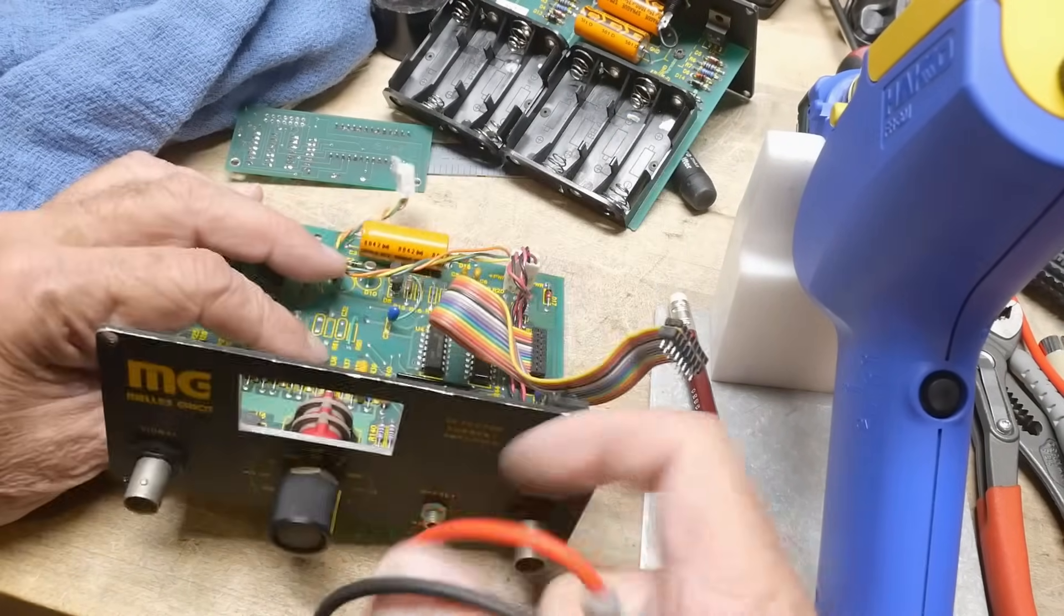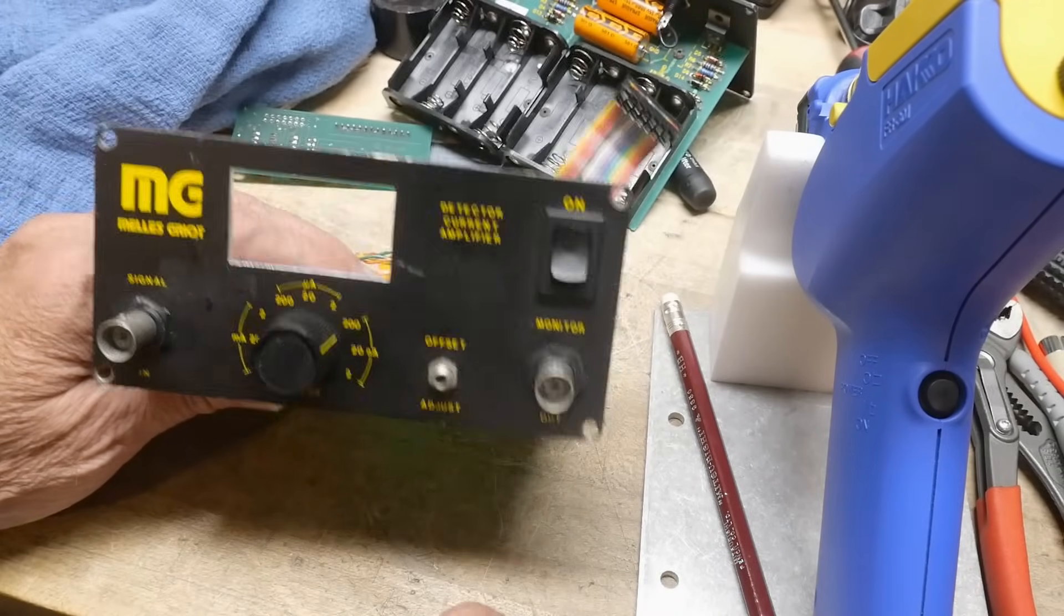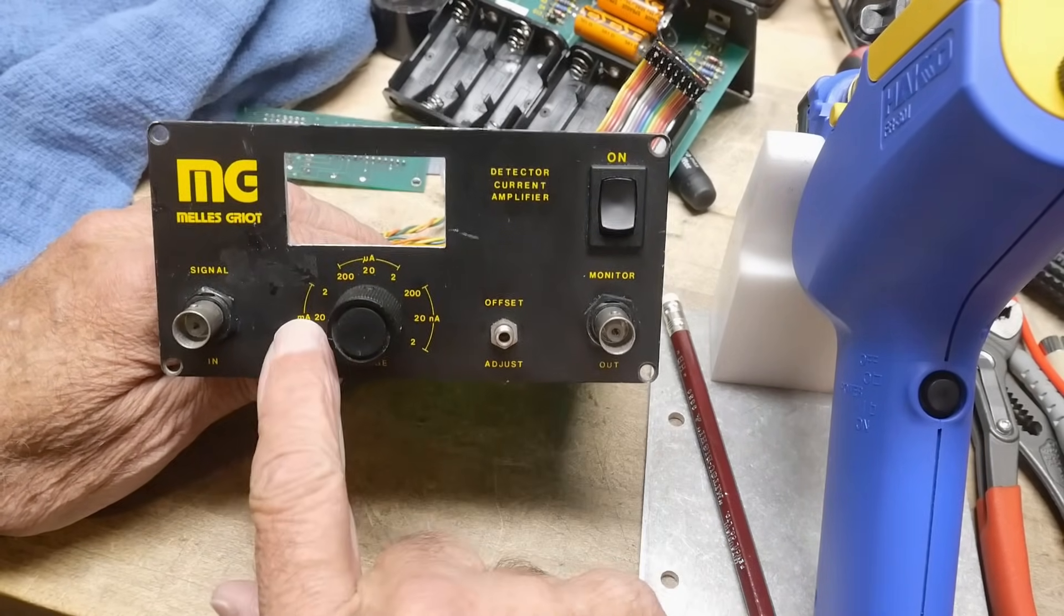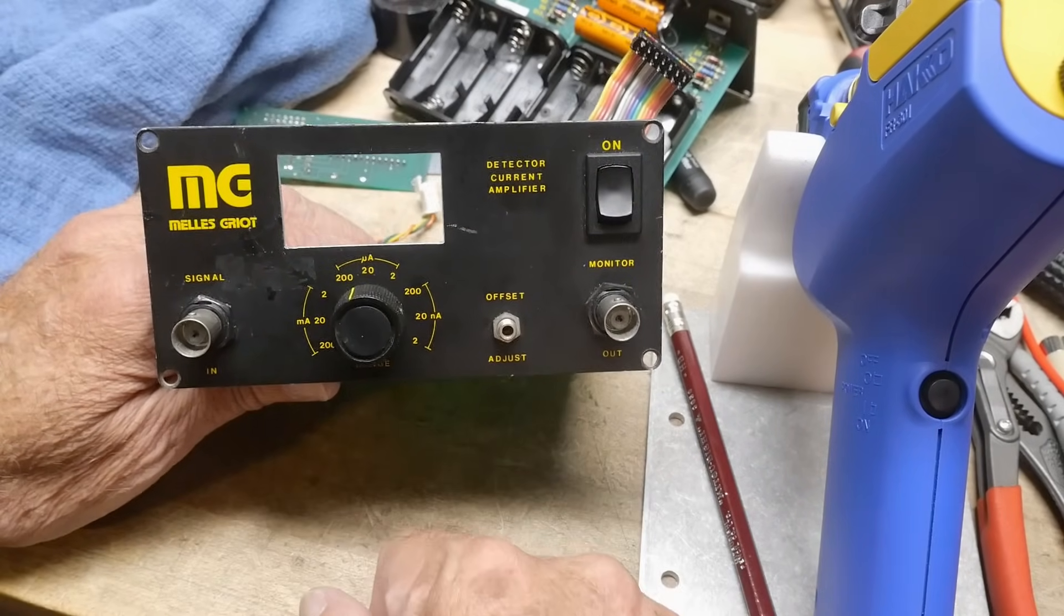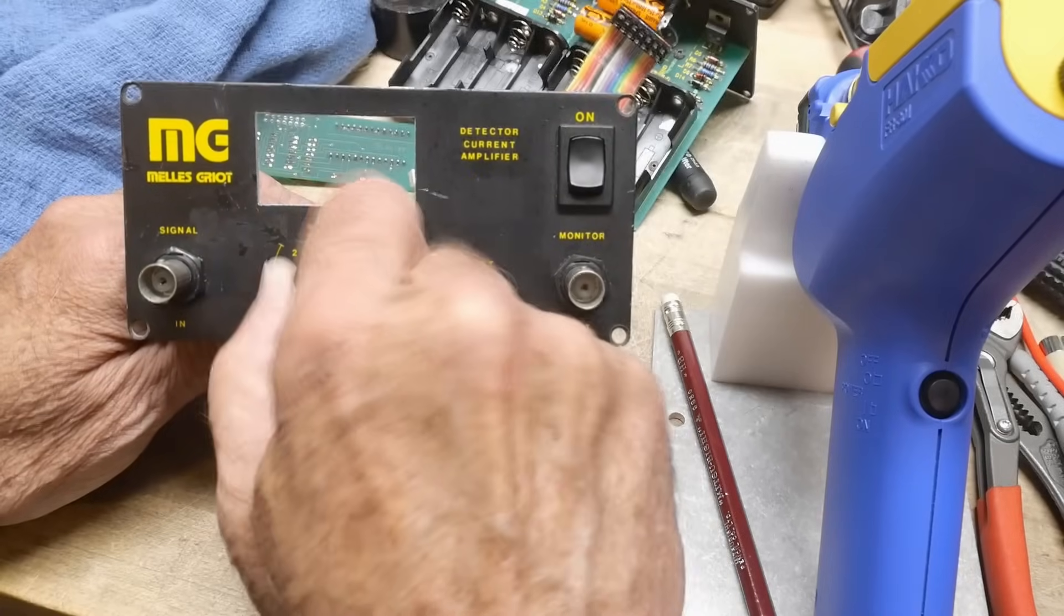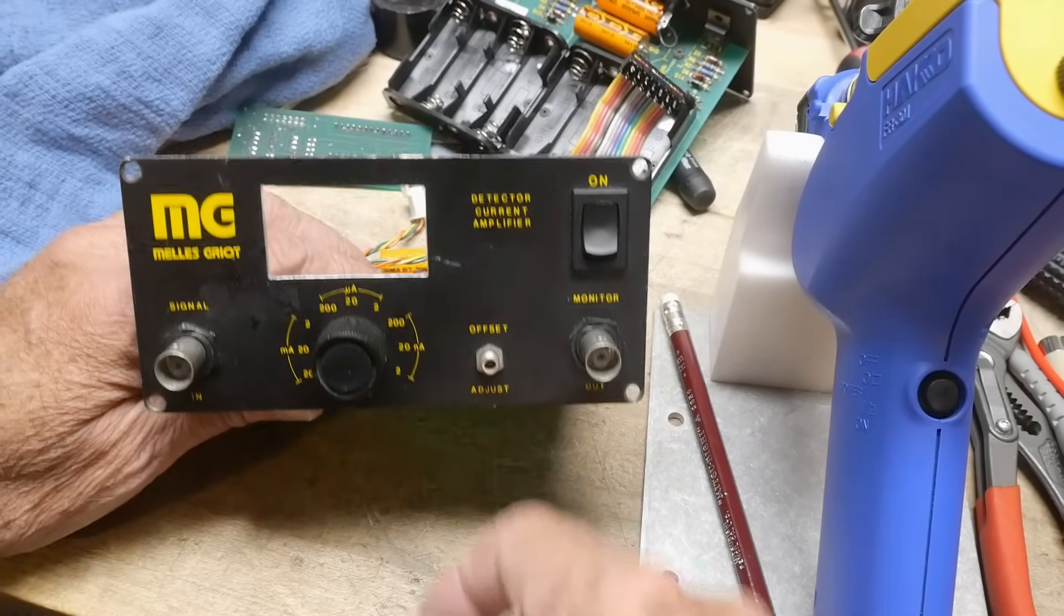So this connector has logic level signals. There's a logic level signal that comes true when you're on the milliamp range, one pin that comes true on the microamp range, and one pin that comes true on the nanoamp range. There's another pin that's true whenever you're at a 200, either that 200, that 200, or that 200. There's a pin on here that's true if you're on the 20s, and there's a pin on there that's true if you're on the 2s.